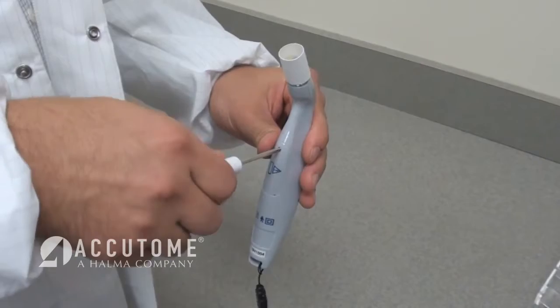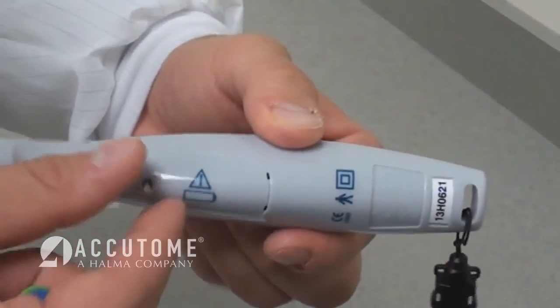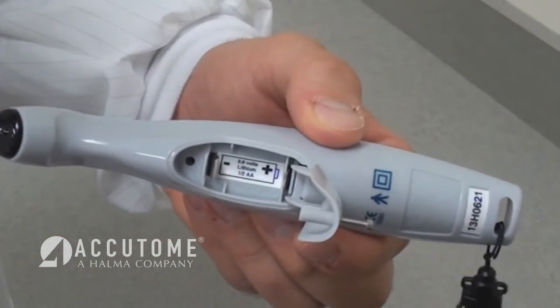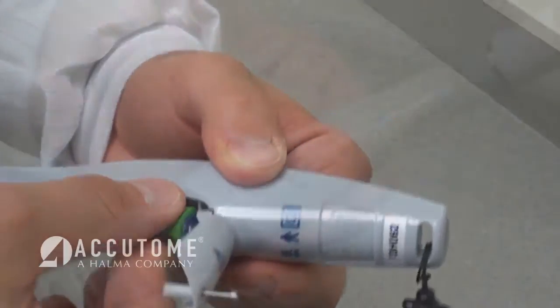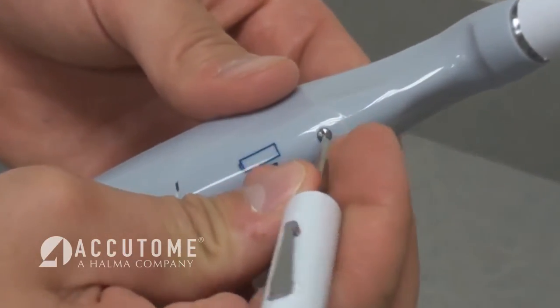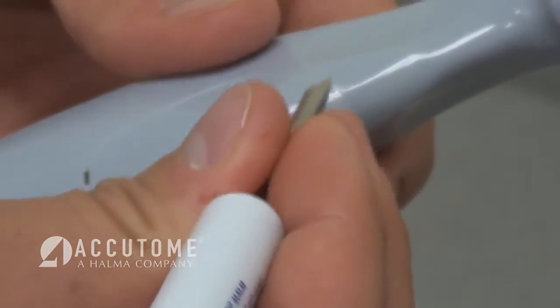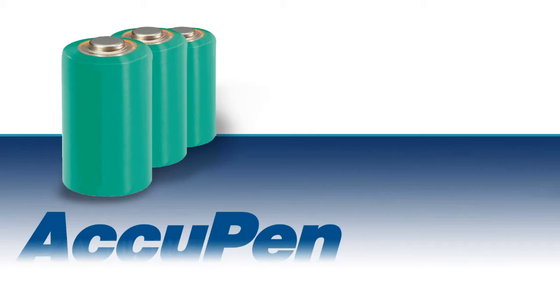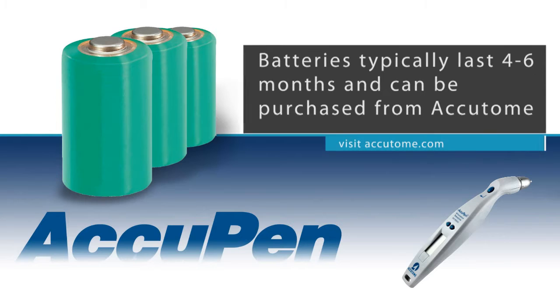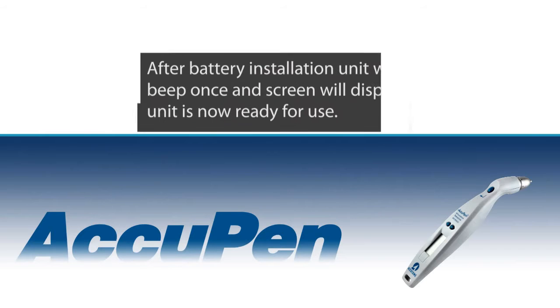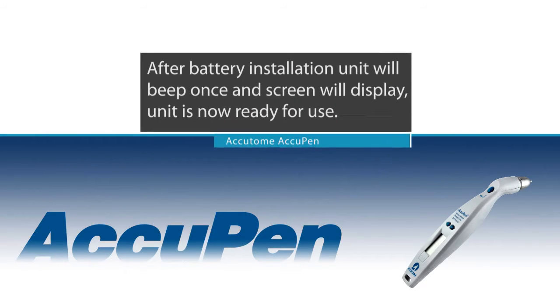Take the flathead portion of the screwdriver, open the battery door, and place the battery inside of the unit. Use the screwdriver to tighten the compartment shut. Be sure not to over-tighten the screw. Batteries typically last 4 to 6 months and can be purchased from AccuTome. Once the battery is installed in the unit, it will beep and give a display on the screen. The unit is ready for use.